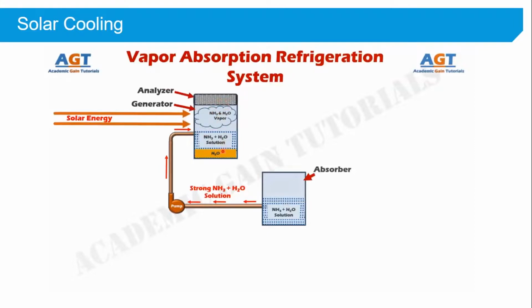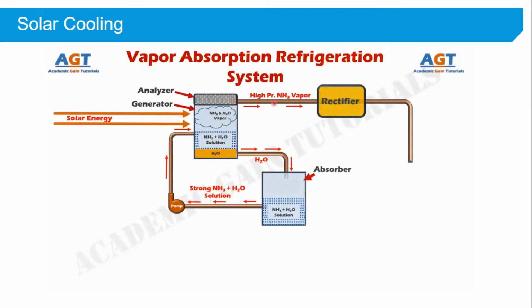Then from this generator, the residue of water vapor accumulated here will be passed back to the absorber again through this connecting pipe. Now, even after passing through the analyzer, there will be some proportion of water vapor mixed with this ammonia vapor. So, here we have a rectifier. This rectifier can also be called a separator, because it separates the rest of the limited amount of water vapor present inside this ammonia vapor through the exchange of heat.